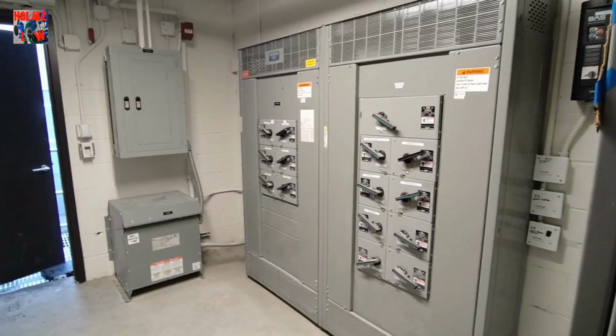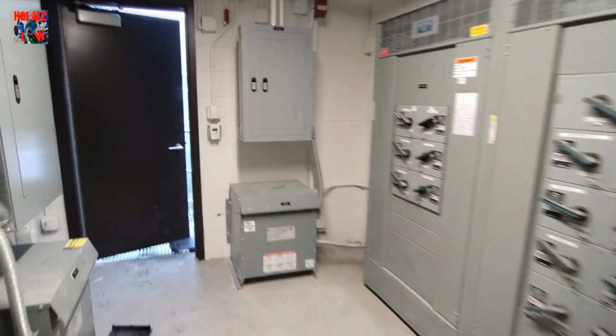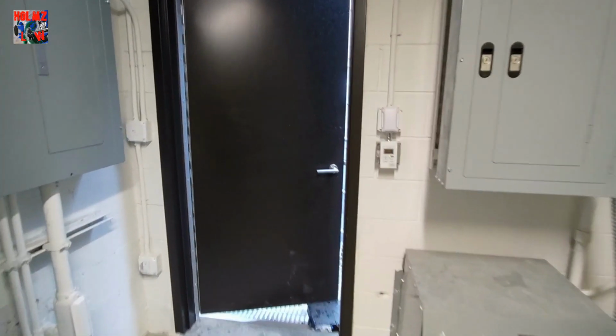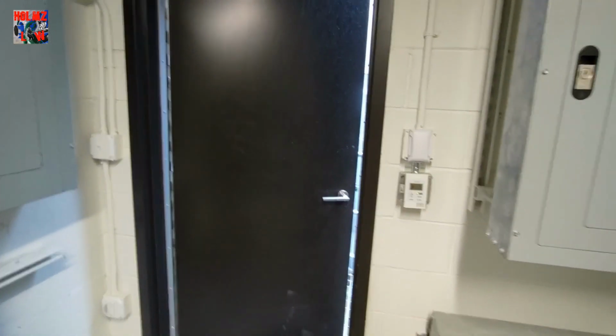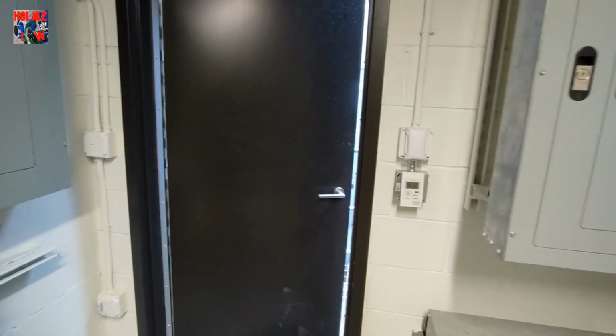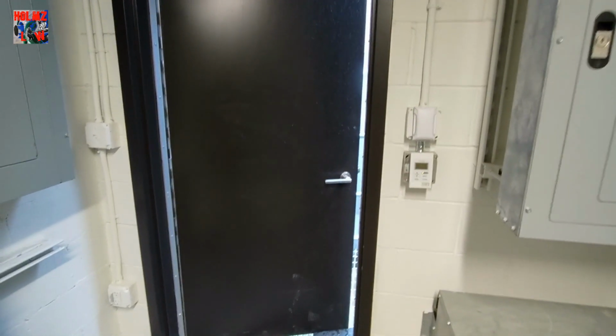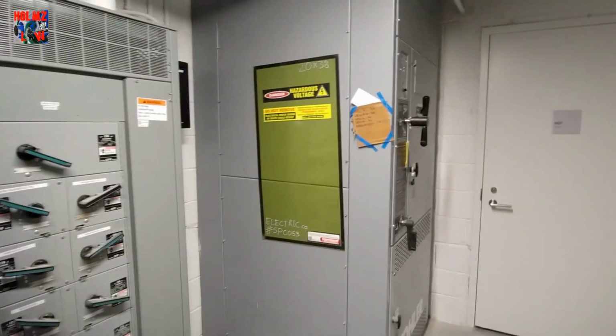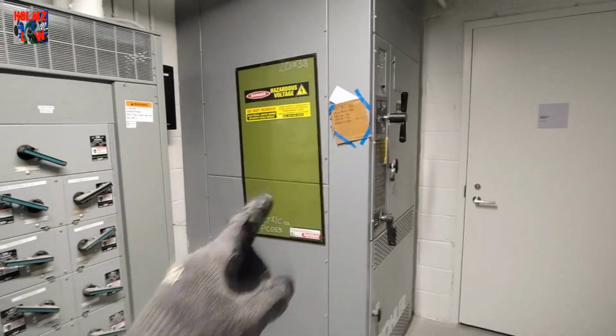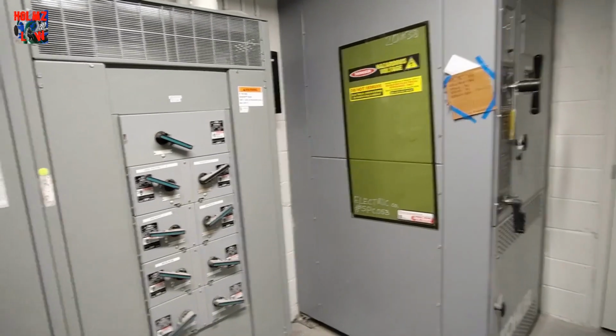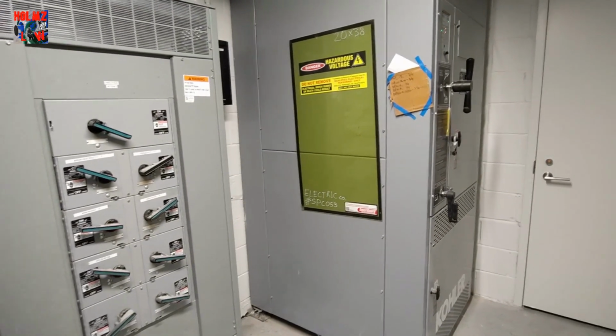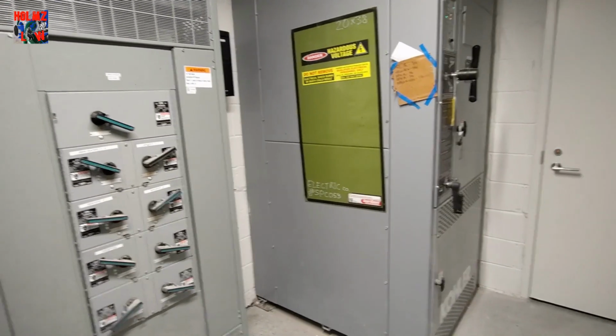So you can see it. All right, and that's what you need to have when you have a generator that's going to be a separately derived system. Now, if you didn't have a four-pole switch, then you would have to unbond the generator, which would be that bracket that you saw that was bonding the neutral bar with the actual ground bar. That's what you would have to disconnect if you did not have a four-pole transfer switch. All right? So that's how you take care of that. If you only have a three-pole, then you unbond it and there's no problem. That's it.